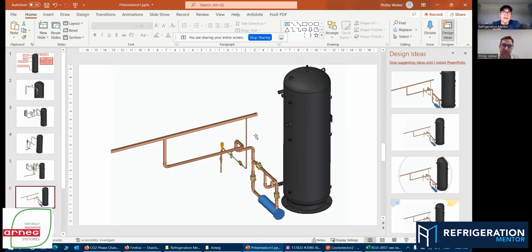You got her. But remember, we're looking at a picture here. The distance span from here to here is not even 2 feet. In all respect, is it going to induce a bit of a pressure drop? Yeah, but we're going to be under a 3-pound pressure drop with this overall design. This is CO2 we're talking about.